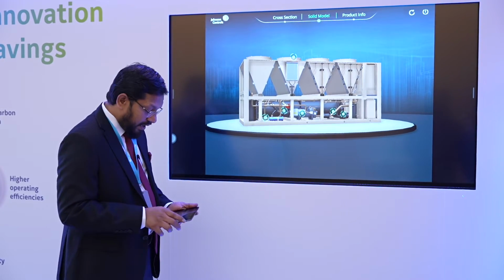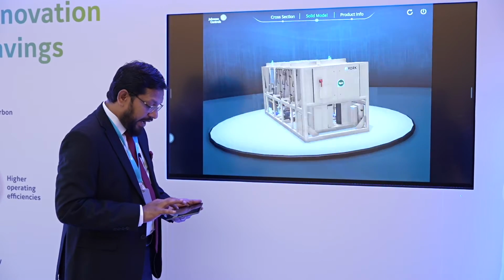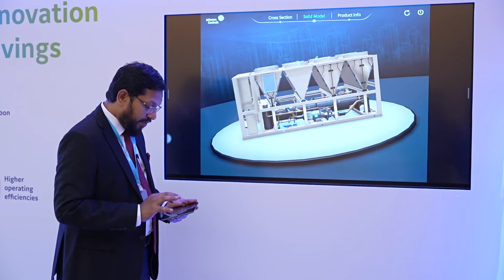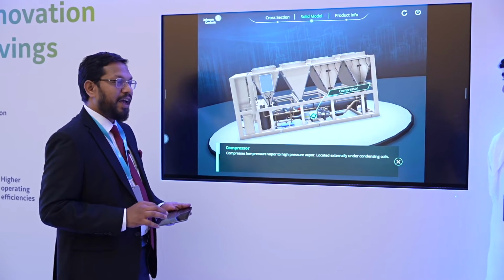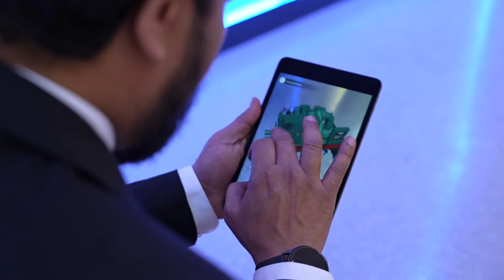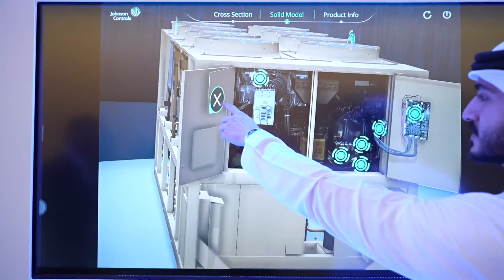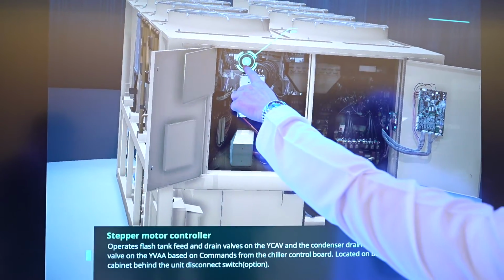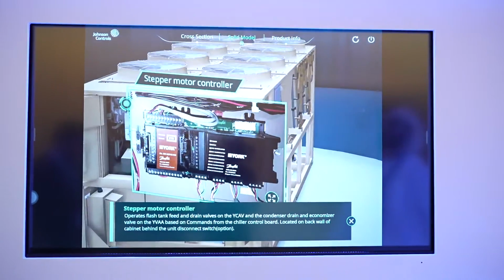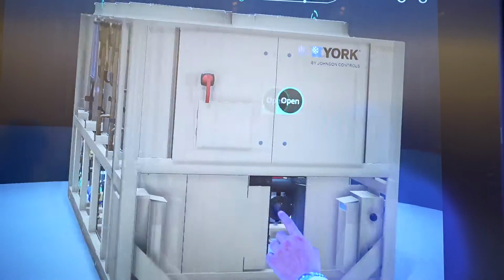And coming to the compressors by itself, in the compressors we introduced the variable speed drive technology, which was never before introduced in an air-cooled machine. What does a variable speed drive do to a chiller? Basically, when we design an air-cooled chiller for a design ambient, for instance, Dubai has a design ambient of 46 during peak summer conditions as per the municipality's regulation. Why do we have to select a design ambient for a machine? It is because during peak summer time as well, we don't want anyone to have an effect on the cooling.